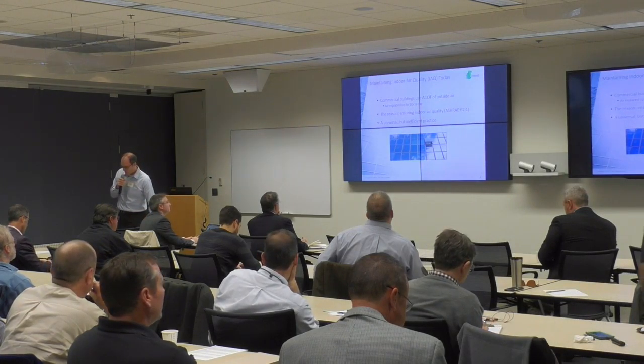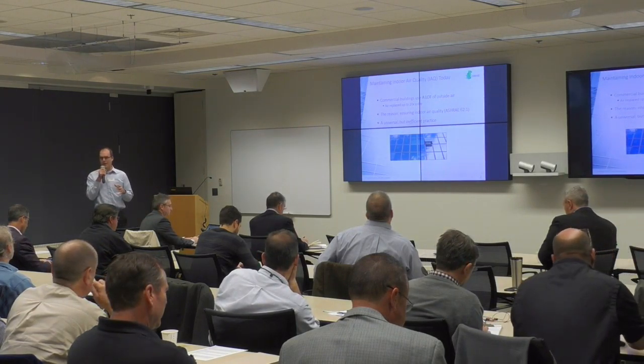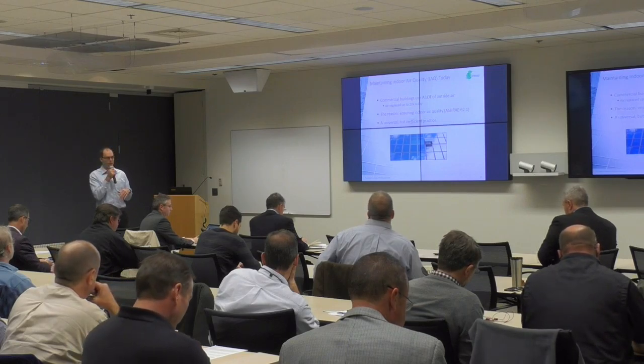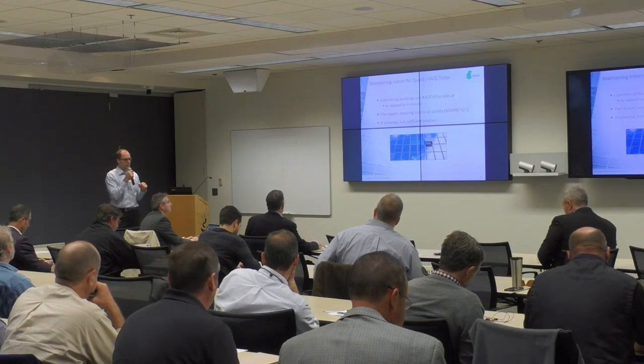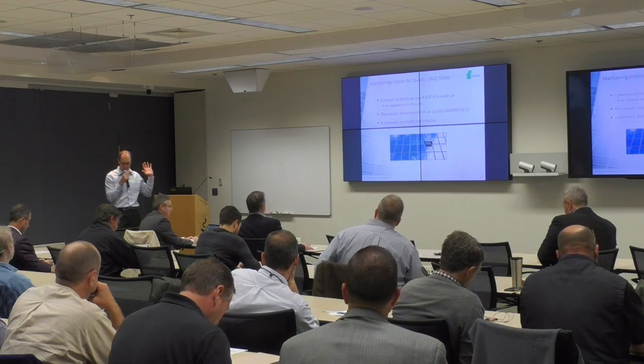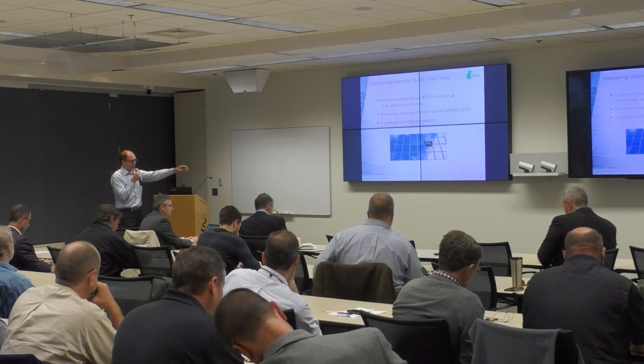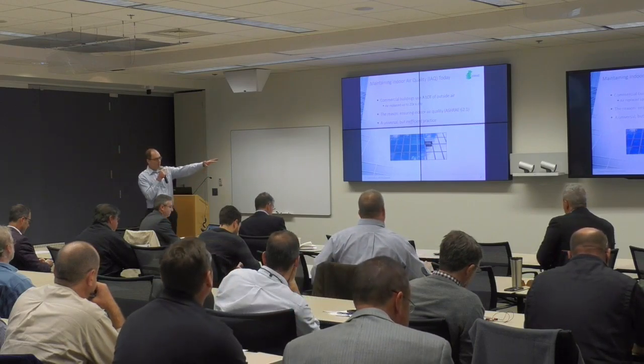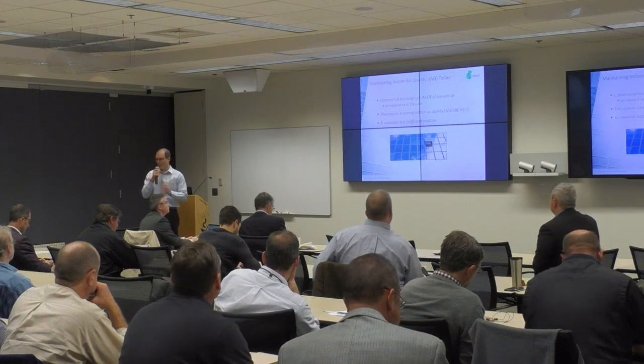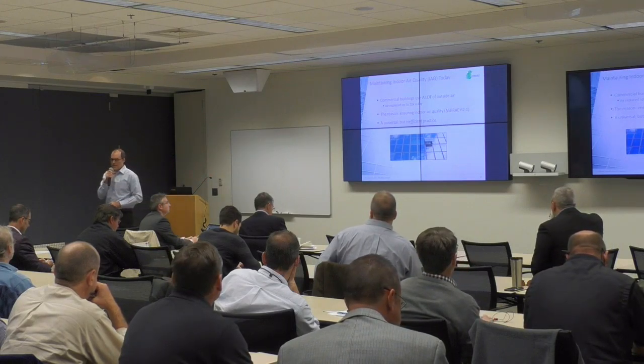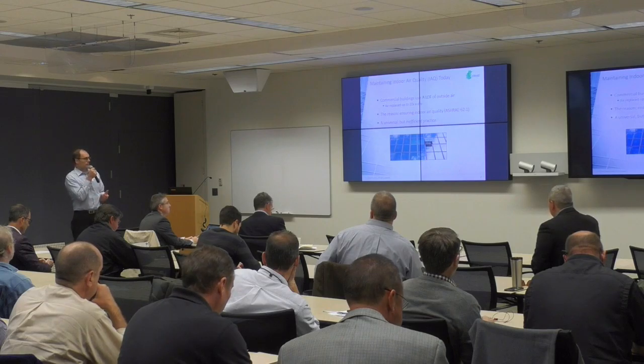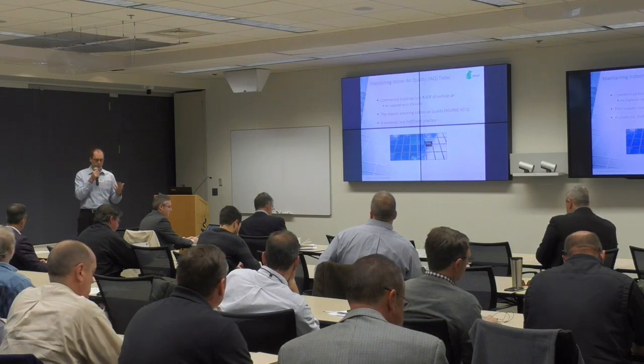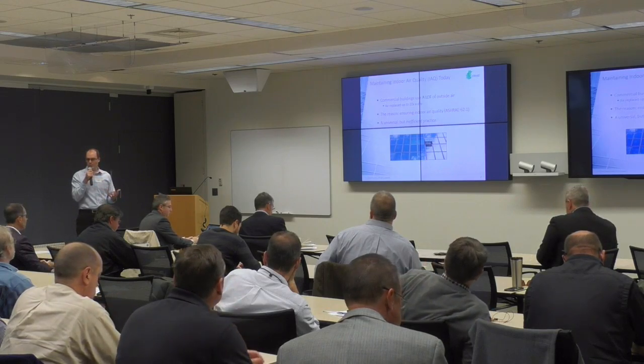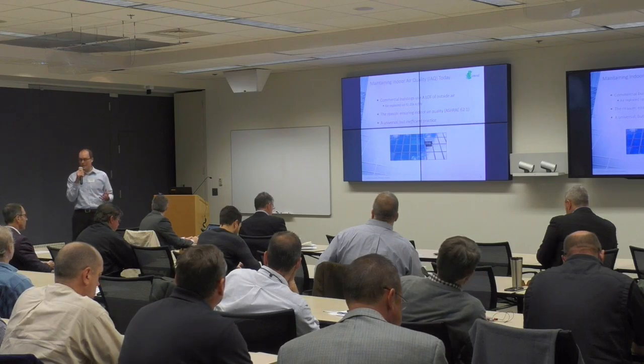As you know, commercial buildings use a lot of outside air to maintain indoor air quality. The ventilation rate procedure means you've got air blowing in all the time. It's kind of like having a window open on every floor with a fan blowing air into the building, and that's to maintain air quality inside. You're typically replacing the air inside the building multiple times a day. We've seen as high as 20 times in a day.